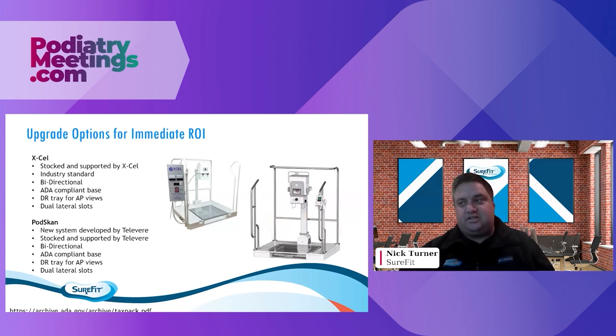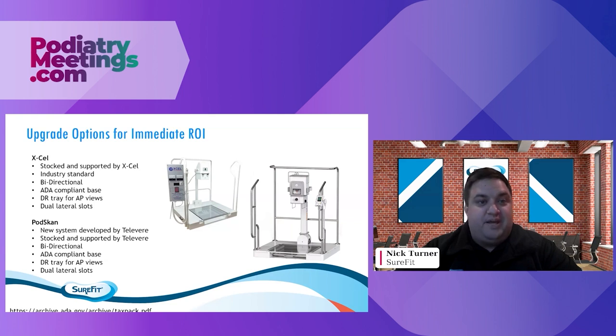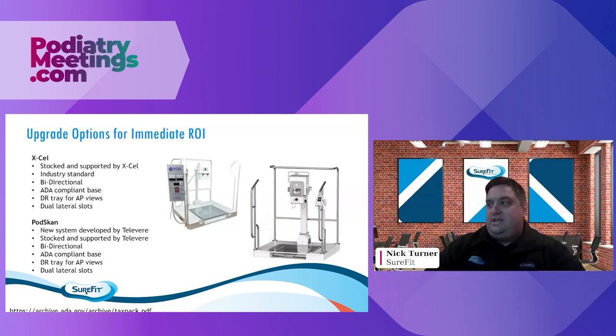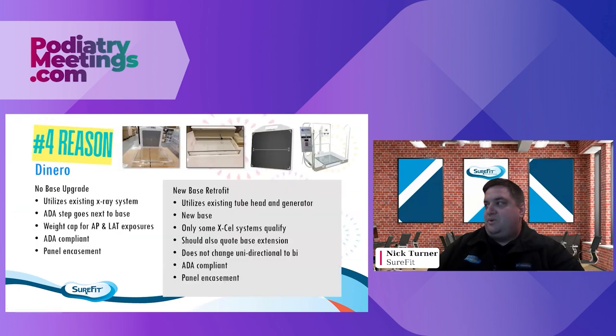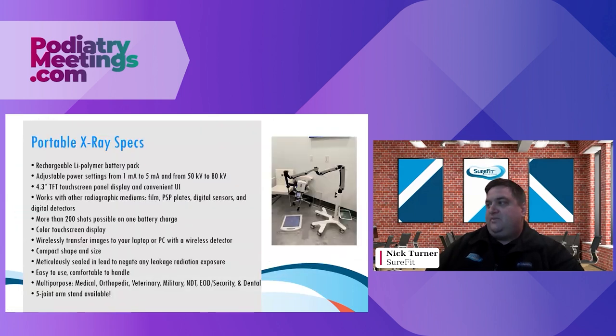That's fairly significant. To the question of what makes it ADA compliant, two parts to that. First and foremost, base height - the base height for ADA compliance needs to be 3.5 inches or lower. This newer base meets that. It's really the base, not as much this piece, not the tube head or the actual X-ray head itself. Where it comes into play with the mobile piece, if you look in the photos, it's actually two parts.